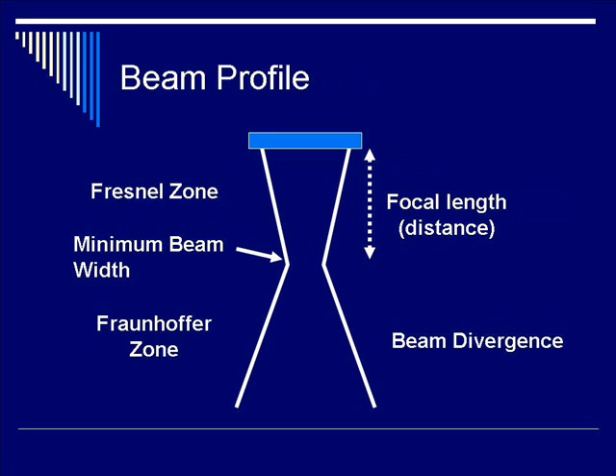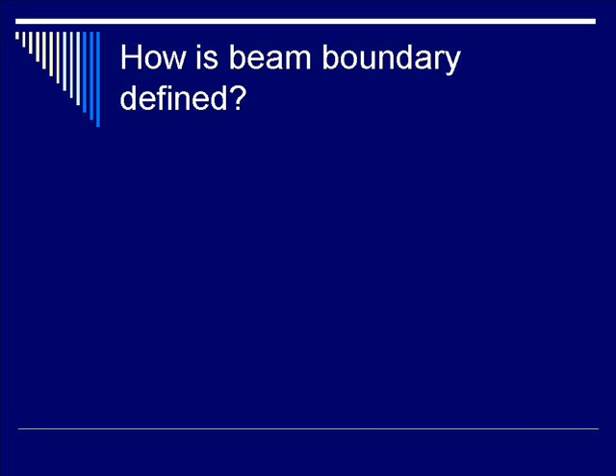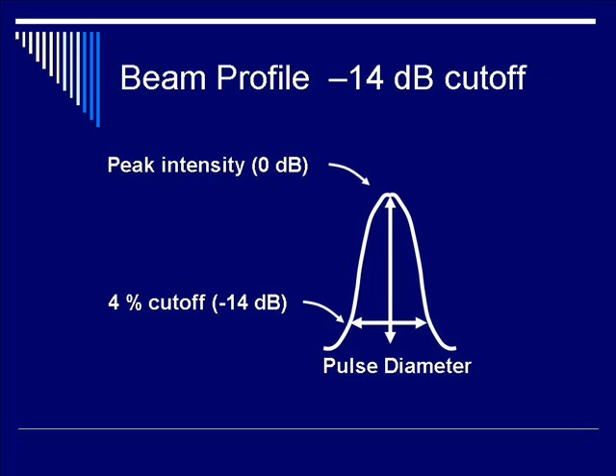The waist of the beam is where beam width is minimum. From that point on, the beam diverges because of a loss of focus. For a single piezoelectric element transducer, a focal zone is defined whereby the width of the beam during this length is less than or equal to two times the minimum beam width. This also can be used to describe a system with a transducer array or one with a fixed lens. Beam boundary is defined using the 10 dB times log of the intensity equation. When the intensity is minus 14 dB, the boundary's intensity is 4%, and that's where we define the boundary. To clarify, a minus 14 dB cutoff implies that for a beam peak intensity of 0 dB, the boundary is where it is minus 14 dB or 4%.